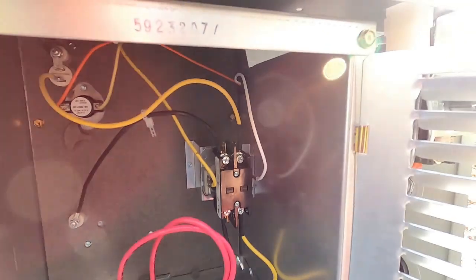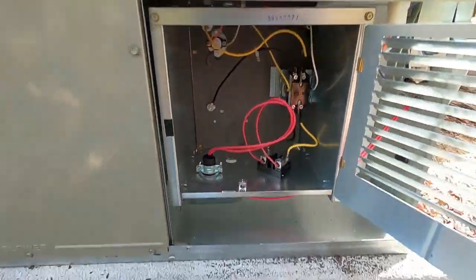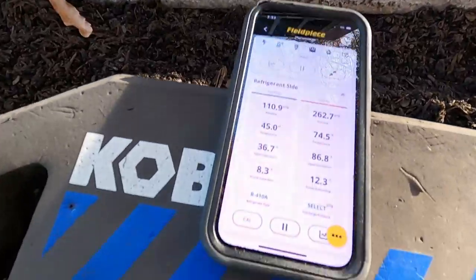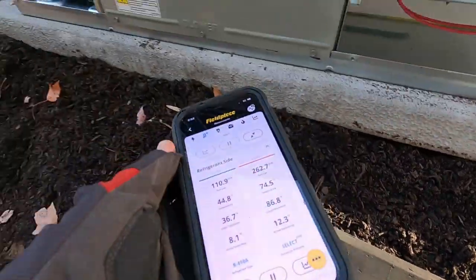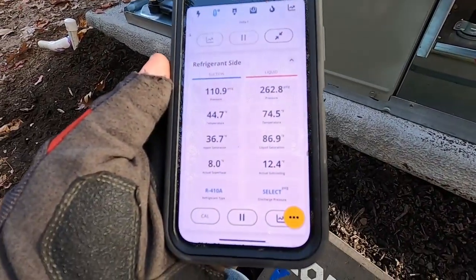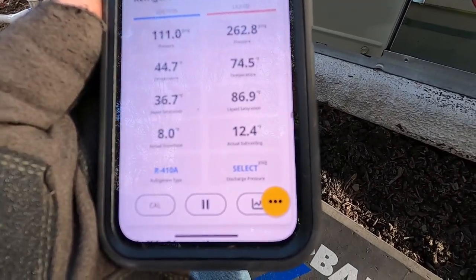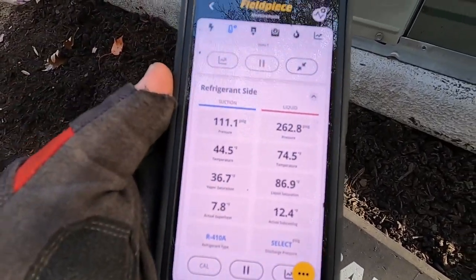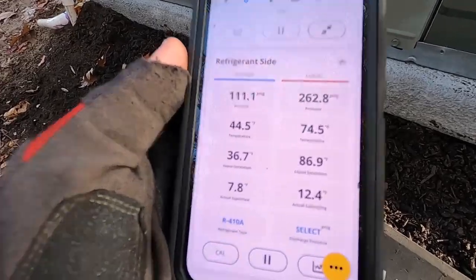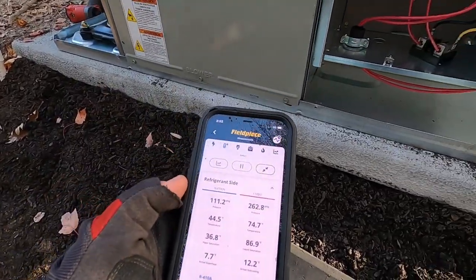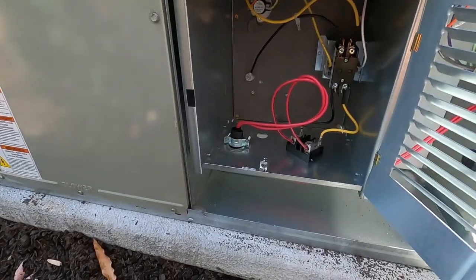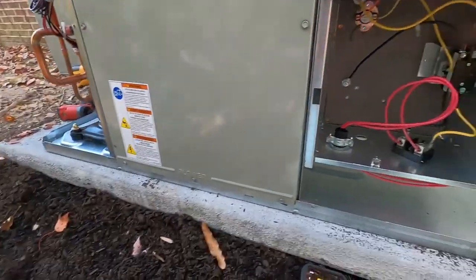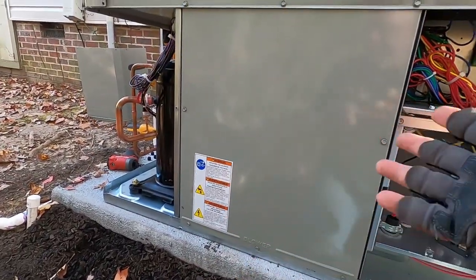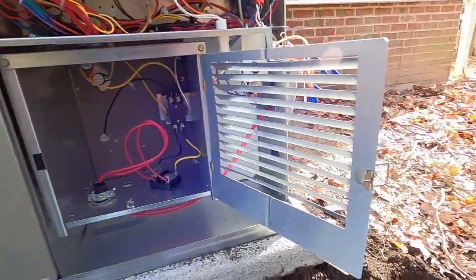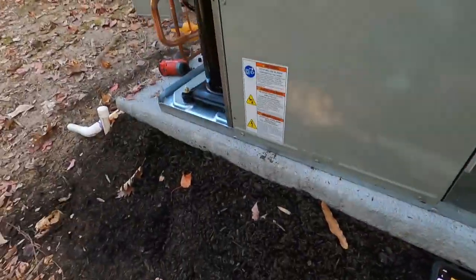But anyway, not worried about all of that right now because I've got the air conditioning running. So we are running about an 8 degree, 9 degree superheat, 12.5 subcooling. It's probably cooling down in the house pretty quick. Charge is looking good in cooling mode. We'll grab some amp draws on the compressor and the fan and the blower. We'll check the temperature split on it, make sure that's good.